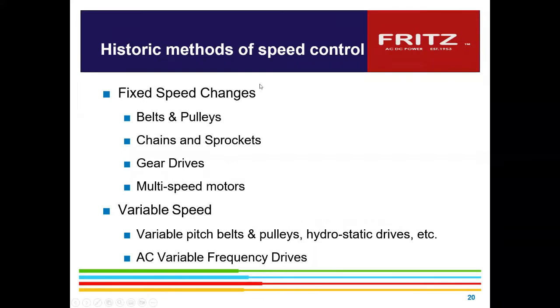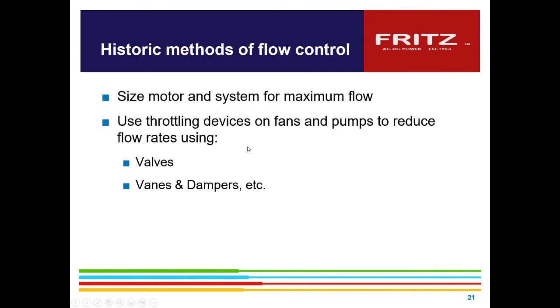When the engineers would do it, they always have to give themselves a service factor. So most generally I see about 125% service factor. So you end up running the fan and the pump a little bit higher than what you need just to get it out, and then you damper it with some sort of a damper. They also use chain sprockets, gear reducers, variable pitch pulleys, and variable frequency drives can also accomplish that power reduction.